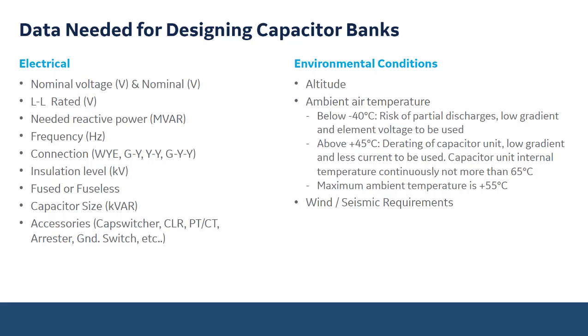And so here we get a lot of questions on how do capacitors operate at elevated temperature, and is there a life expectancy decrease due to elevated temperature? And this is something we get asked pretty frequently by a lot of our southeast or southwestern customers, and the answer is capacitors operate in elevated temperatures as expected. There's not really a decrease in life expectancy due to that elevated temperature.